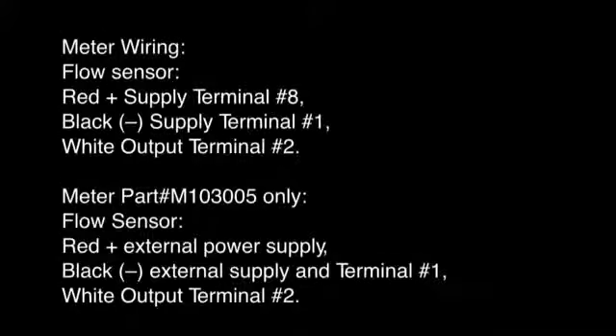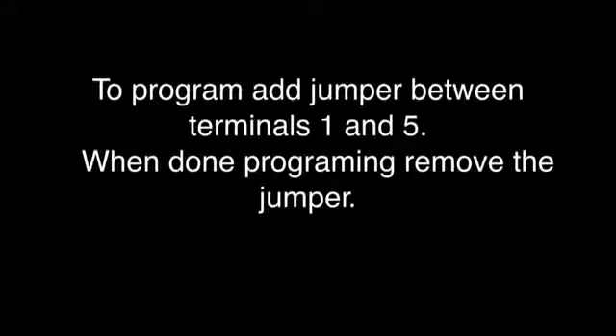How I know it is, there's two ways: either on the spec sheet, or also every meter comes with a manual explaining how to do this. Another thing we have made up is a little cheat sheet. The main thing is knowing how many pulses you can program it. When you actually go to program it, you don't need the sensor wired to it. You do need AC plugged into the meter, and then your sensor wired into the meter can be done later on. To actually do it, you need a jumper between terminal 1 and 5, and that lets you into the calibration mode. So when you're in the calibration mode, let us go through it. There's going to be 6 steps.